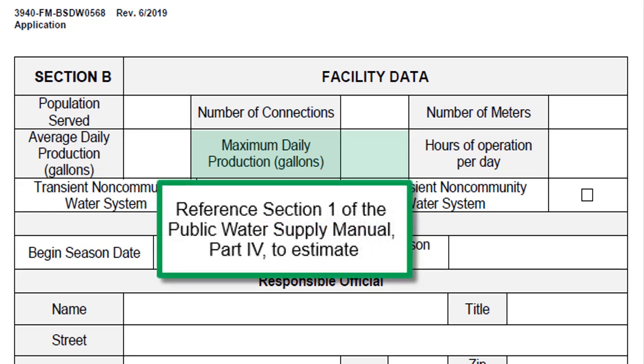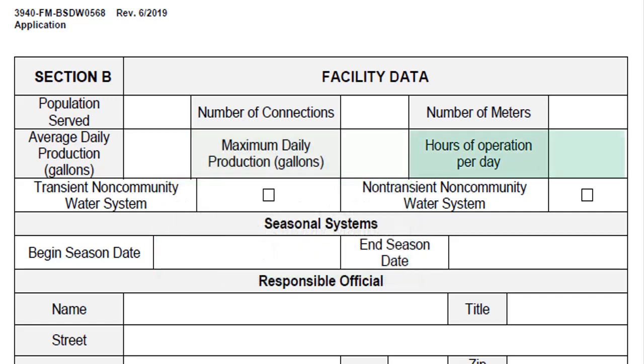Back to Section B of the application, the number of meters includes the total number of connections equipped with a meter. Average daily production is the average volume of daily production in gallons based off of the most recent calendar year. Maximum daily production is the maximum volume of water used in one day. New systems, or systems that don't have information on their maximum production, should reference Section 1 of the Public Water Supply Manual Part 4, Non-Community System Design Standards, to estimate the maximum daily production. Hours of operation per day are the number of hours the treatment plant is normally operated each day — for a hospital this may be 24 hours, whereas an office building may only be open for 10 hours.